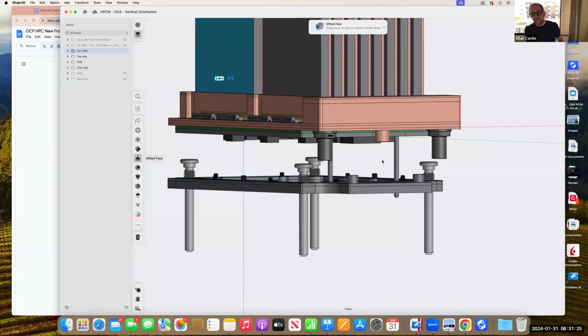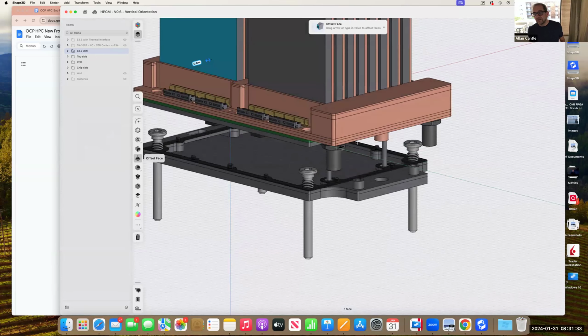Now, the only other piece we potentially had on this is we wanted to control the flow. I'm just thinking one phase for a minute, because two phases may complicate this. We wanted maybe some flow control inside here, like a little motorized valve opening and shutting the amount of flow going around, because we wanted the ejected water to always be maintained at one temperature, ideally 65°C, so we can do energy reuse without any additional heat pumping.